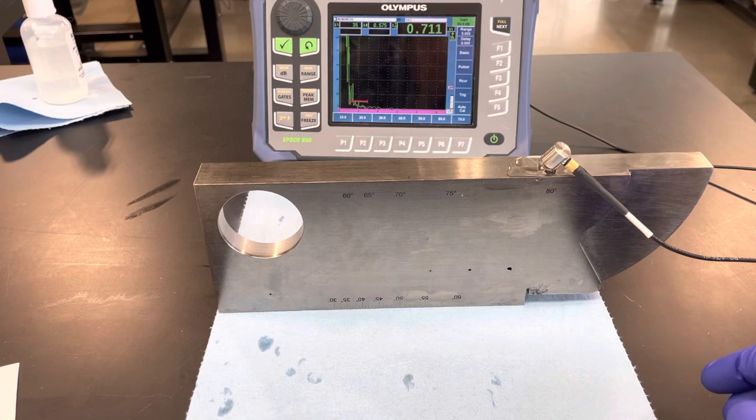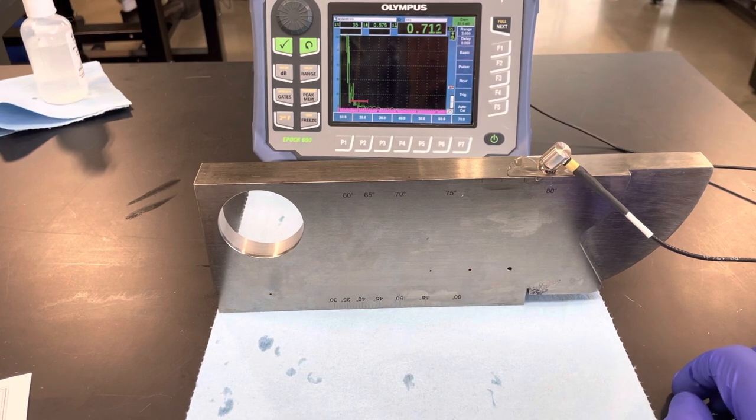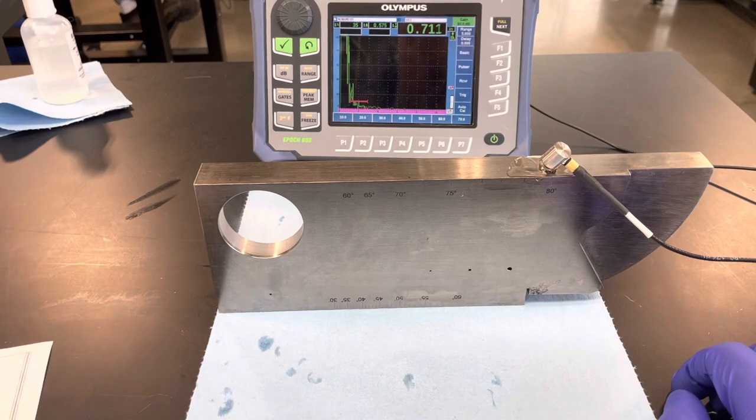We have a 2.25 MHz transducer using Epoch 650, a type 2 steel IIW block, and our gain is at 60.